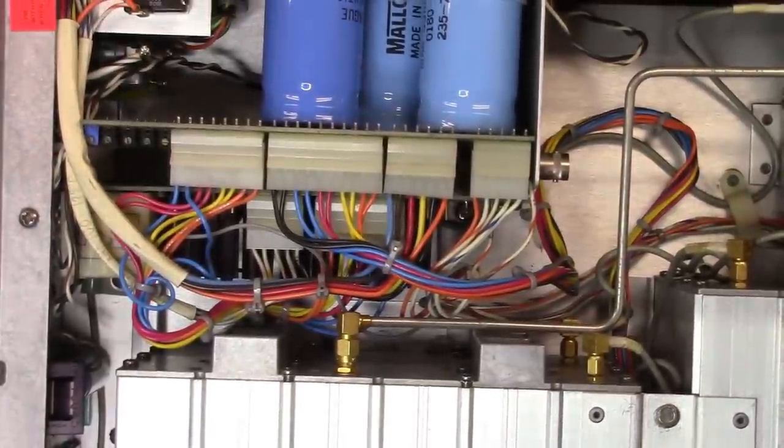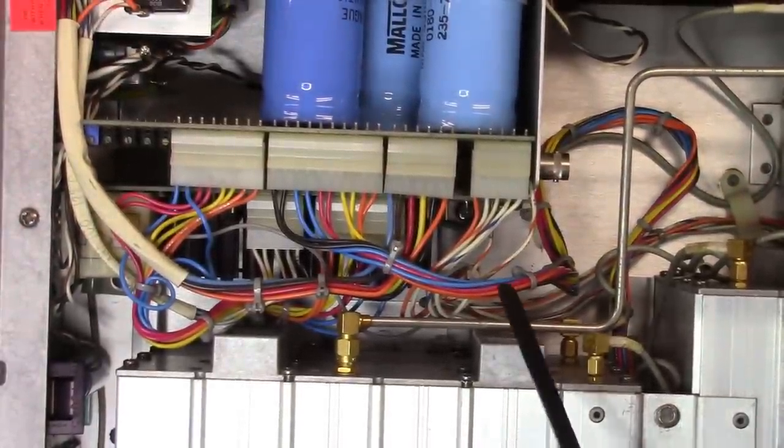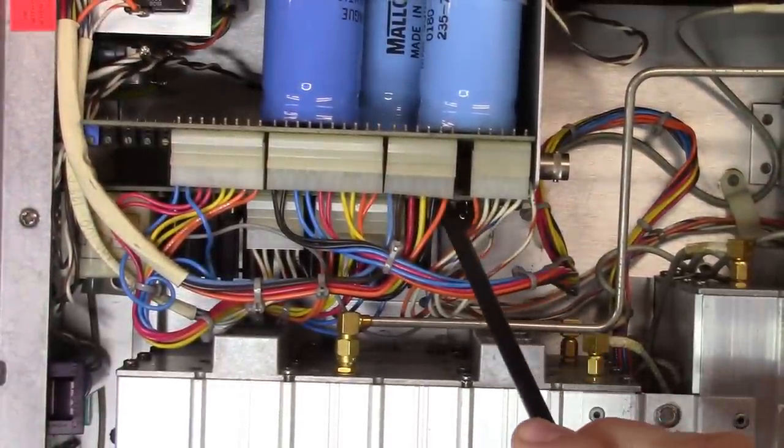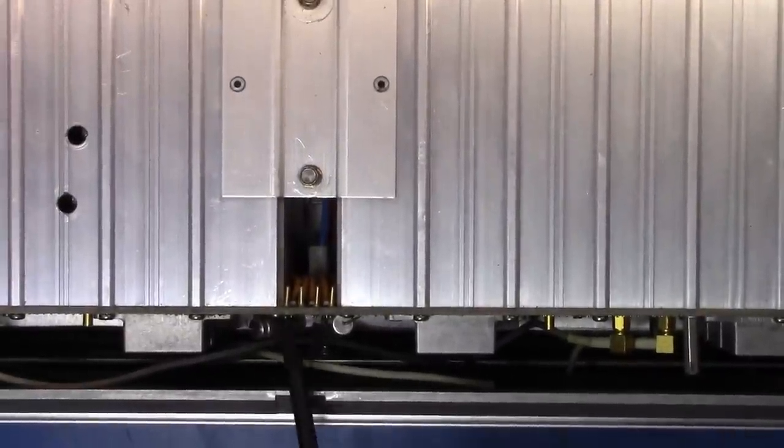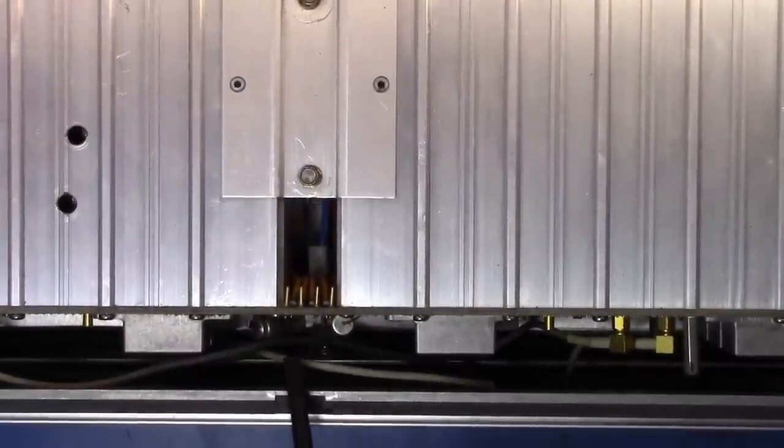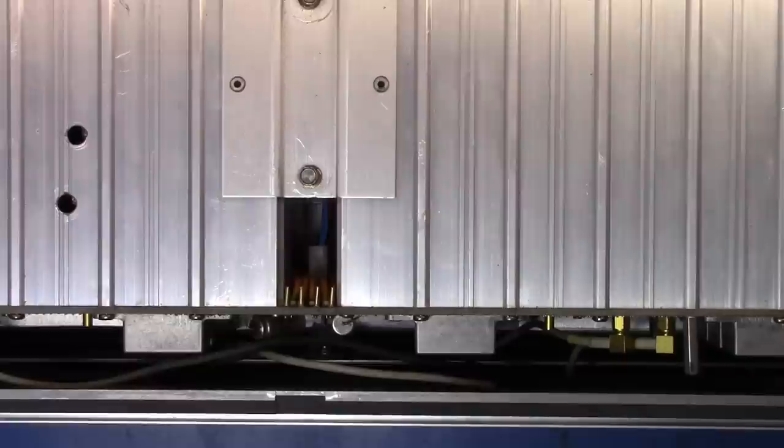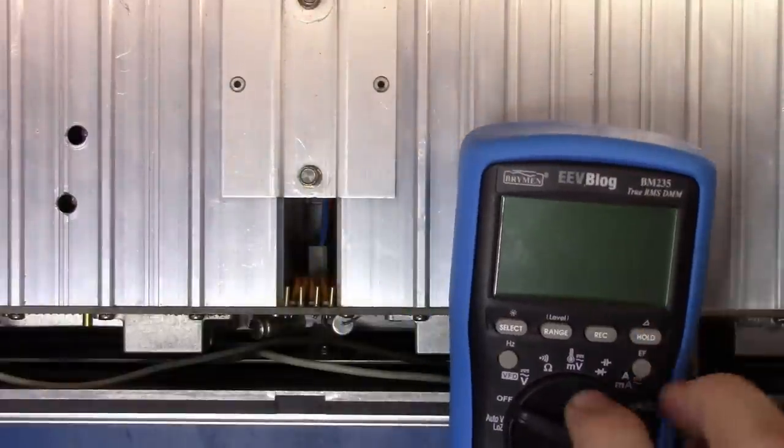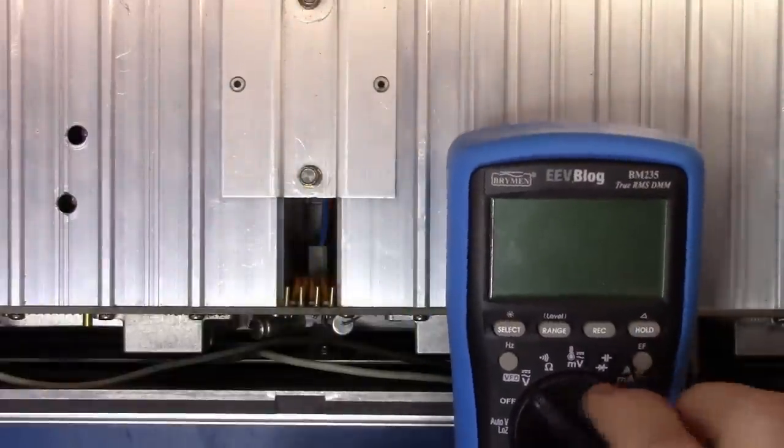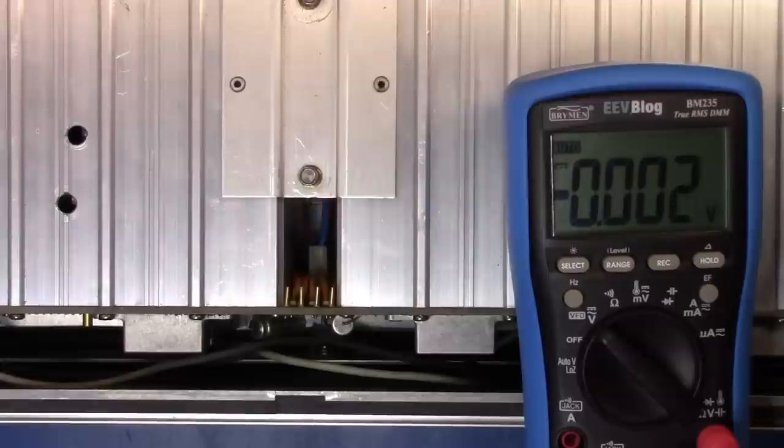Okay well after having looked in, the boards that we should be looking at is actually, eventually be measuring here if there's a problem with that. But what the manual says to do is to check the four rails that are here on the motherboard. And so we have the minus 5.2, plus 15, minus 15 and plus five volts here. And so we can come in and check those. So let's just turn the unit on.